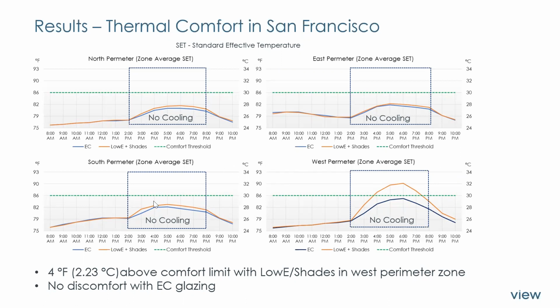Once the HVAC turns off, the air starts mixing and heating up. The effect is more localized in the west perimeter because the system stops from 2 to 8, but you can see it in the other zones too. Clearly though, it's not really getting into that discomfort threshold if we assume 86 is our threshold, which I said earlier is fairly high - it's like 1.6 PMV, that's like 50% PPD or something.